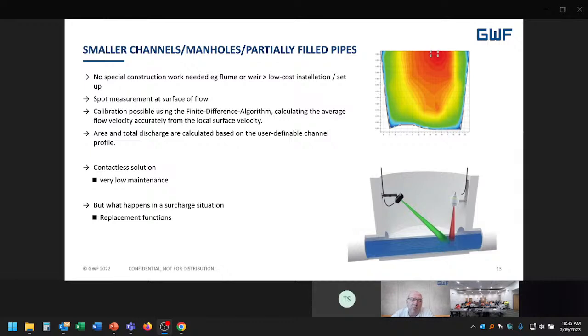So when we put these types of sensors in, they have to be calibrated. We calibrate ours by actually defining what the shape of the channel is, and based on the surface velocity that we measure in that one point, and also a level sensor, we're able to then accurately calibrate for what's going on within the channel. So we're actually calculating where there's going to be slow flow, where there's going to be fast flow, and how it's going to relate throughout the cross section of the channel.